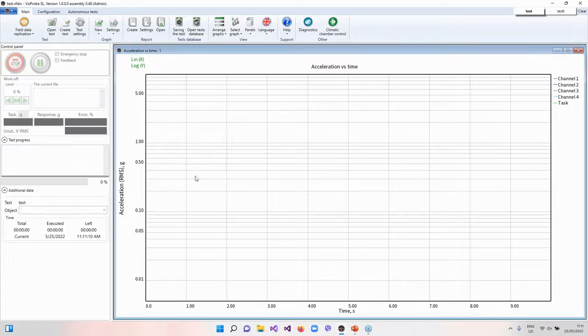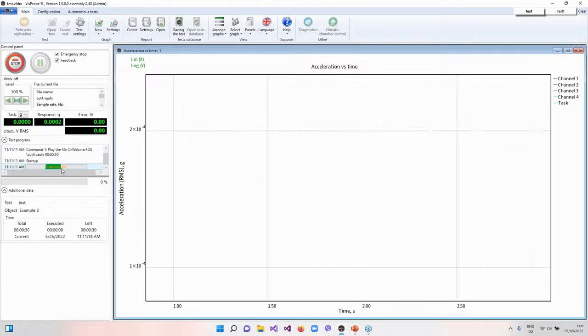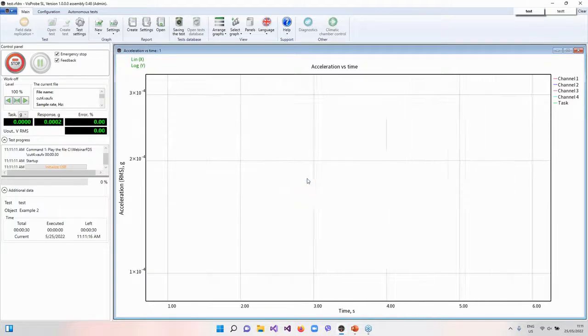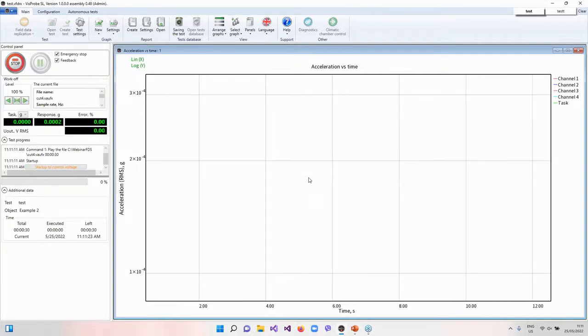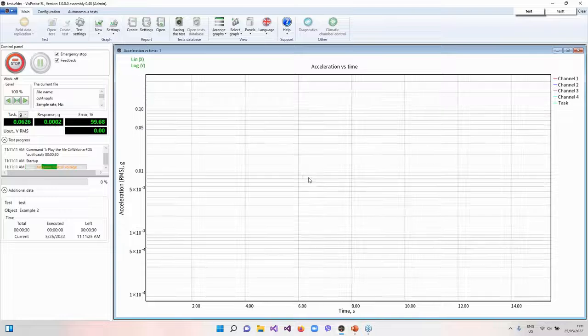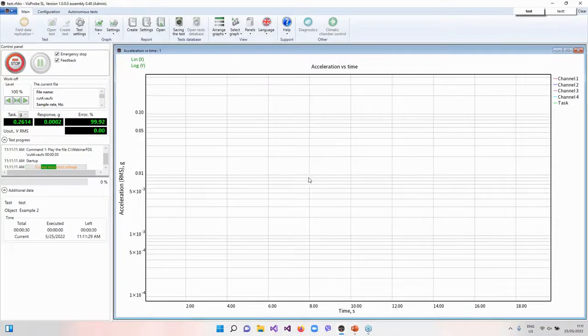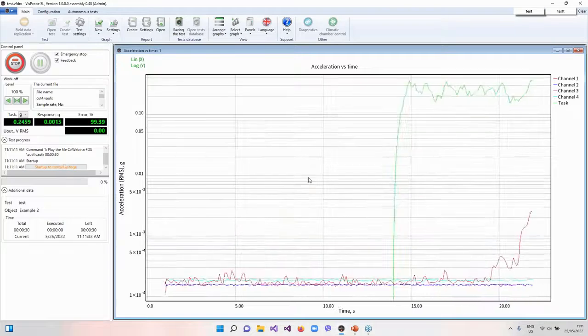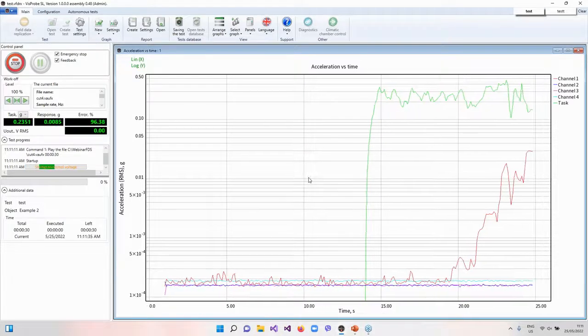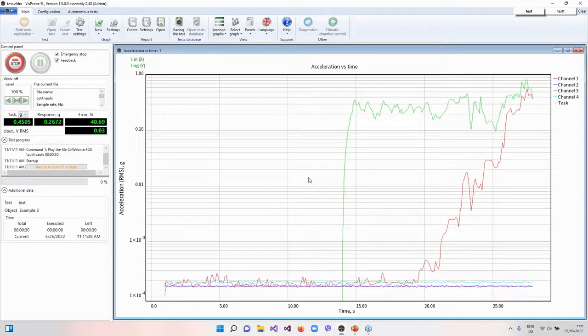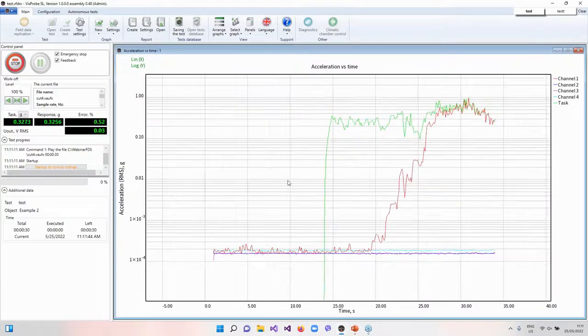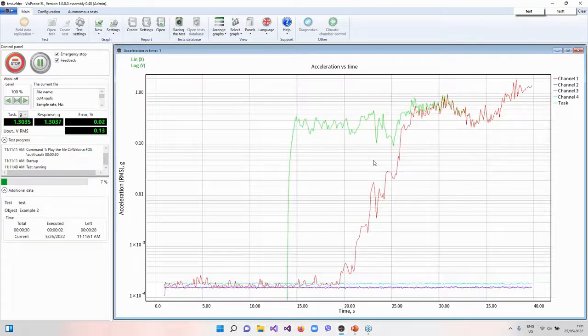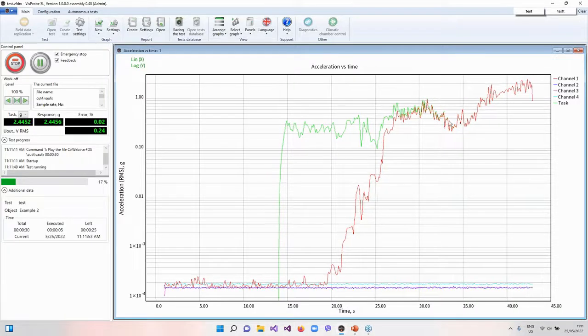Let's start. Here you see that our system is starting up. Let's scale the graph a bit. During the field data replication test you have an ability to run the recorded signal from your device on your system and create a vibration test using this signal. You can replicate real-life events using this test. Here you see that we are near startup voltage, and here we are running our test.